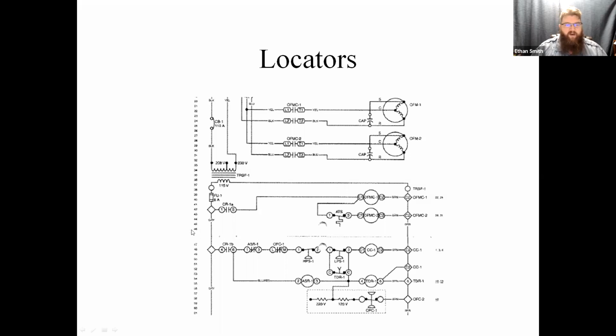22, 24. Come over to the right-hand side of this wiring diagram and you'll notice that every line is numbered. So we know that on this line, we've got a component that services something on line 22 and line 24. If we come up to line 22, we'll notice that line 22 lines up with this OFMC1 designator, and it's got a set of normally open contacts. This is the OFMC1 relay, so these are my OFMC1 normally open contacts. Line 24 lines up with the other set of contacts from OFMC1. This becomes really handy for diagnosing, because we can literally go through something in a very linear fashion and find out where it goes.